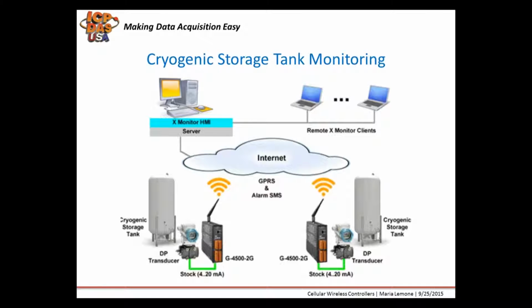Cryogenic liquefied gases are stored in special pressurized storage tanks at very, very low temperatures, down to negative 180 degrees Celsius, which is negative 292 degrees Fahrenheit. Very cold. These gases include liquefied nitrogen, oxygen, and argon. Tank level measurements are taken with a specialized calibrated differential pressure transmitter with a 4 to 20 milliamp output connected to the analog input of the M2M controller.